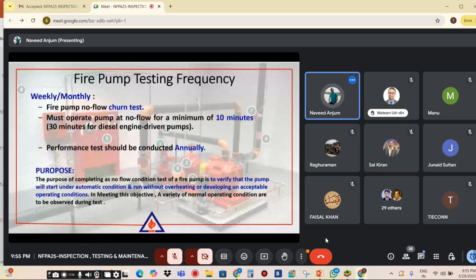You must operate the pump at no flow for a minimum of 10 minutes, and 30 minutes for a diesel engine driven pump, and a performance test should be conducted annually. Every year you have to check the performance. In performance testing, you have to check 3 points, which are mandatory. You can check at 4, 5, or 7 points, but 3 points are mandatory. At zero flow you have to check at which pressure the pump goes, then at 100% rated flow, and then at 150% rated flow. Like if we have a pump of 2500 GPM, we have to check at 3 points. At zero flow we will check what the pressure is.